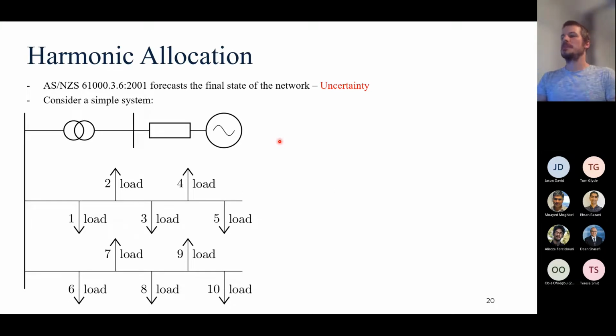So I mentioned 61000.3.6, which has been adopted by Australian standards as a standard, and therefore by law, but it has not reached the level of an international standard by the IEC. So it has achieved the status of a technical report. By definition, a technical report is ultimately a bunch of good ideas. Something that needs to be used with sufficient engineering judgment, and a good understanding of the implications of the decisions that you're making. And the experiences and the discussions that we've had here in Australia suggest that's not actually happening.